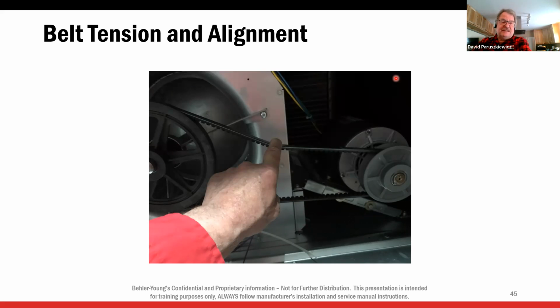So even with all that said, these belts are loose and they need to be adjusted. Our static is not factory set. We need to adjust the static. When we get calls out to a job, the belts are damn near falling off and the thing's tripping on limit. Guys, this is part of your startup. You have to do this. These units are not set and run out the door. We need to check this.